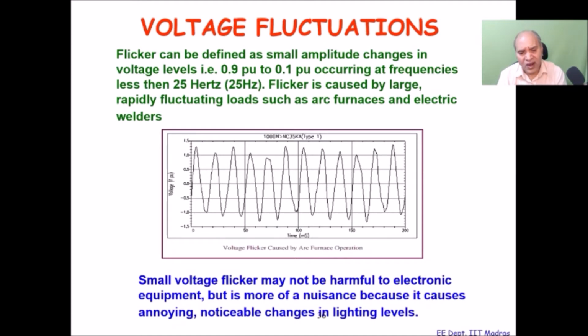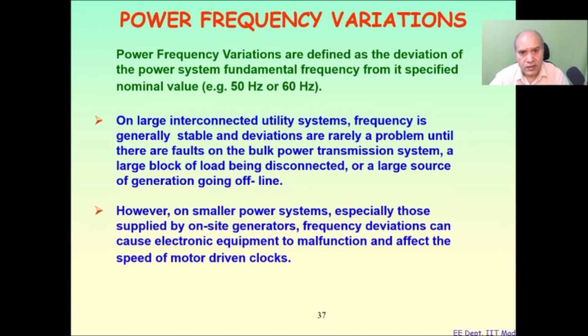They may not be very harmful to electronic equipment, but it is more of a nuisance because it causes annoying, noticeable changes in lighting levels. So when you read or do some work, you feel annoyed because it is changing in magnitude and frequency. Power frequency variation. Power frequency is another fundamental parameter of the power system to monitor its health. Normally the power system frequency should be around the fundamental frequency, 50 or 60 Hz.